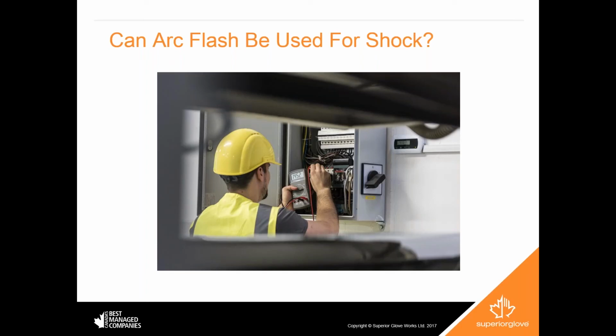So start out, can an arc flash still happen if there's no exposure to energized conductors? This is a question that's come in a few different ways it's been written. Some people have asked if there's risk for arc flash where there's no risk for electrical shock, and vice versa. Yeah, so in terms of can an arc flash still happen if you have no exposed energized conductors? Yes, it can. So things like inserting or removing draw-out circuit breakers, bus plugs, MCC buckets, anything like that, it can cause an arc flash where there normally wouldn't be a perceived hazard.